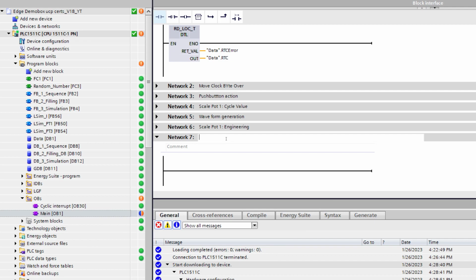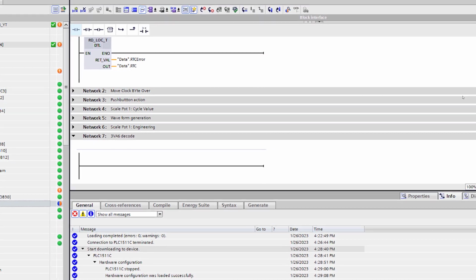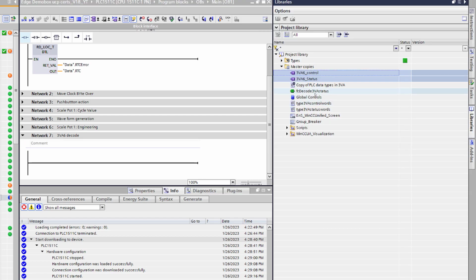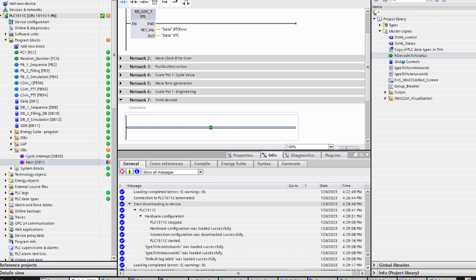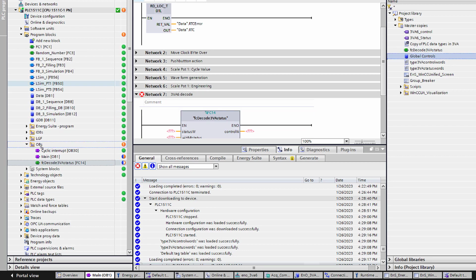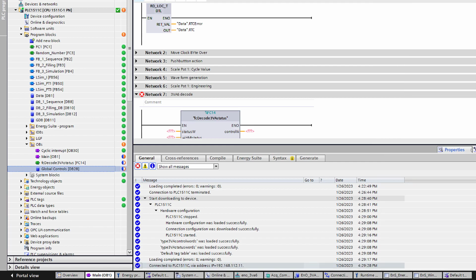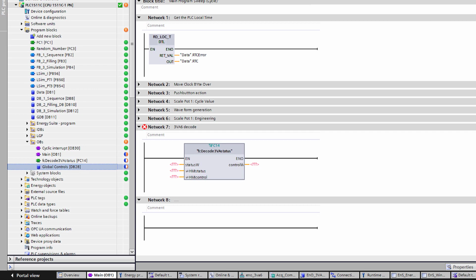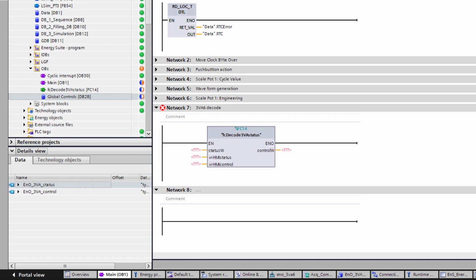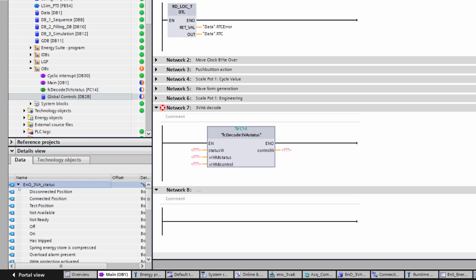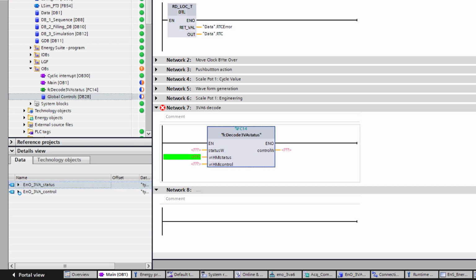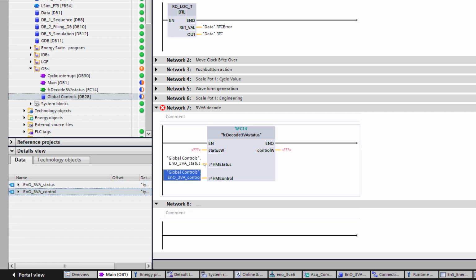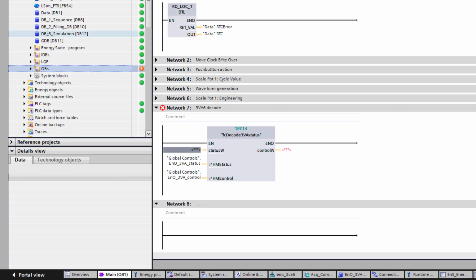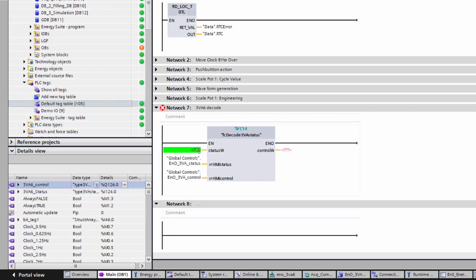The last thing that we need to do is implement a function call for decoding the 3VA6 status that we just read in. And then finally, I'm going to drop in a global data block, which contains the landing spot for our decoded values. It's these decoded values that become useful in the HMI. So highlighting the global controls and dragging the status and control words to the in-out section of my block, along with aligning the status and control words from my tag table, allows the function call to operate without errors.